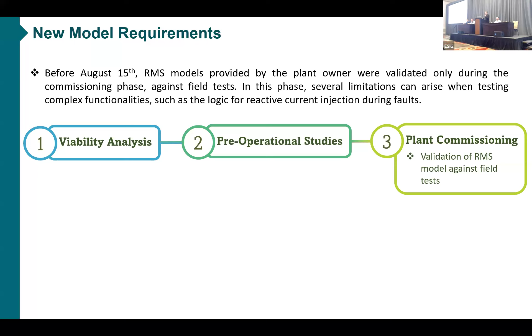And we know that there are several limitations with field tests to test complex functionalities, for example, logic for reactive current injection during faults. So to address this limitation, it will now be necessary to provide, during the pre-operational study, a PSCAD model of the real equipment accompanied by a validation report based either on laboratory tests or HIL simulations. And then the real equipment RMS model will be validated against the PSCAD.